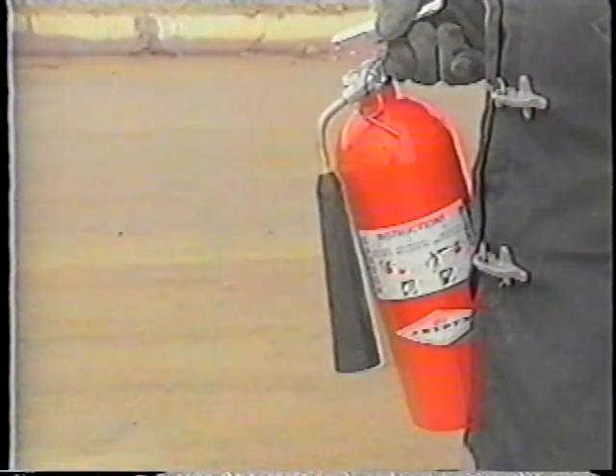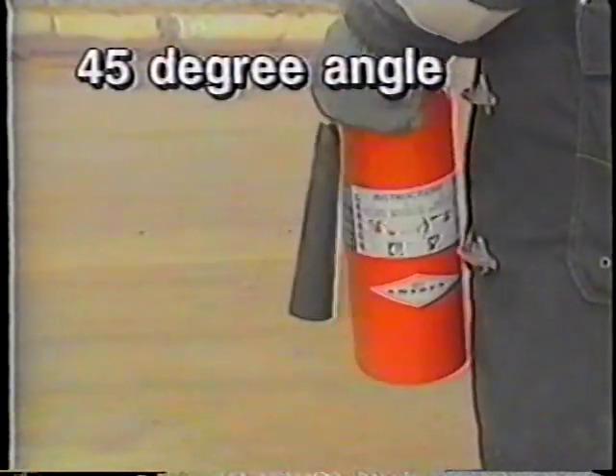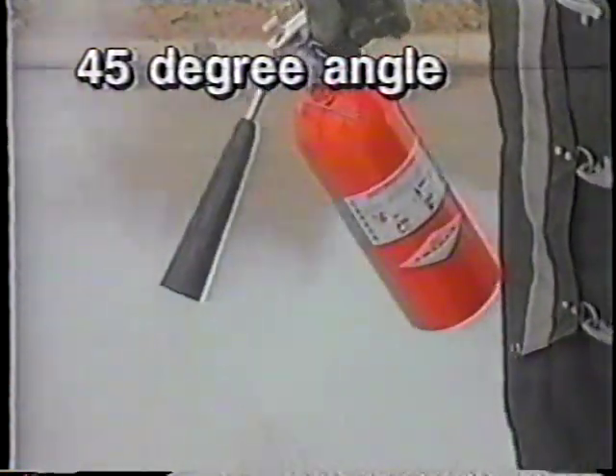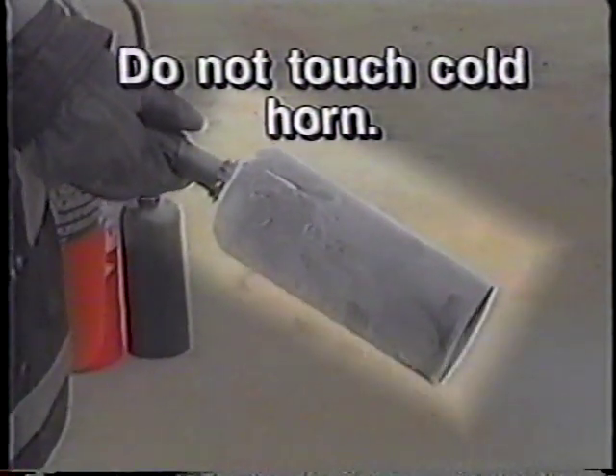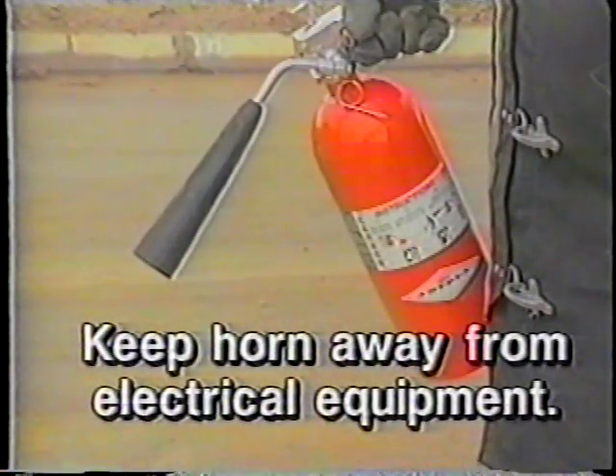For confined fires, an overhead method may be the most effective. Point the horn downward at an angle of about 45 degrees toward the center of the burning area. The horn of the carbon dioxide extinguisher can cause freezer burn if touched during or after use. Remember also not to handle the snow produced by the carbon dioxide extinguisher. The horn can also conduct electricity, so remember to keep it out of direct contact with any electrical equipment.